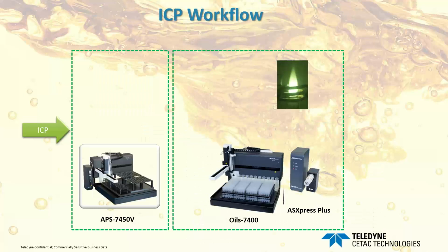So ICP has its own unique workflow. The samples will typically need some additional preparation before they're ready for analysis. Specifically, they need to be diluted. With oil samples, a 1 to 10 dilution with kerosene is very common. Once diluted, the samples are ready for introduction to the ICP instrument, and this task is handled by an autosampler at most labs.